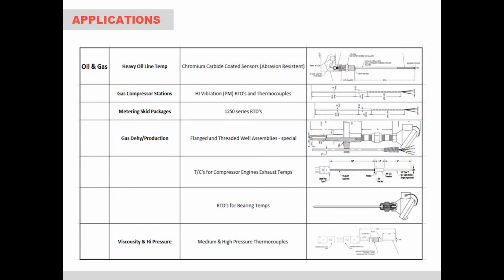Oil and gas applications include a variety of thermocouple and RTD opportunities. Focusing on the thermocouple applications, specialty abrasion-resistant coatings on the MI cable are available. Rugged elements designed for high vibration installations can be provided as well. Numerous flanged and threaded well assemblies are usually required for pipeline measurements and process tanks at compressor stations and gas production plants. Specialty exhaust temperature thermocouples are used for monitoring the performance of large compressors and for high pressure applications such as 5,000 to 30,000 psi. We have a wide range of sensors and the ability to test each in-house using our test stand rated to 80,000 psi.